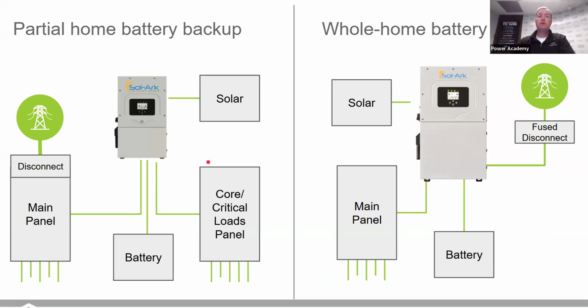Using CTs, we can put CTs in the main panel to measure how much energy is being consumed by these loads, then tell the solar to discharge—not only to supply backed-up loads downstream of the inverter, but also to feed power back to the main electrical panel without exceeding the currently active loads. So yes, you're still backfeeding onto that tie-down breaker at the bottom of the load center, but we're only sending back as much as the home loads are consuming.